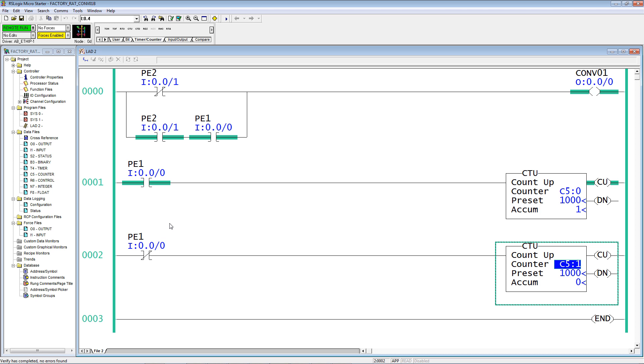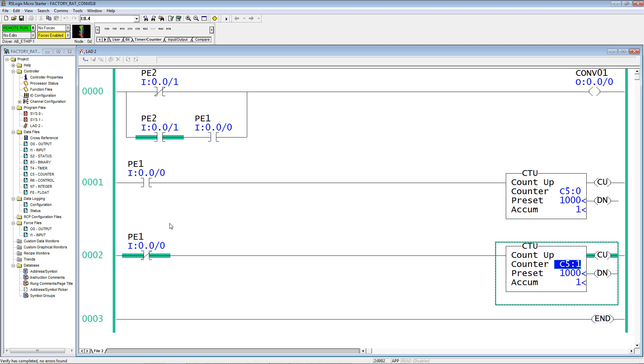Now, as that carton travels onto the conveyor and clears photo eye 1, look down at C5-1 and see what it does when it clears. Now, if you were going to count cartons onto the conveyor, would you count them when they arrived at photo eye 1, or would you count them when they left photo eye 1 and were pulled onto the conveyor? So I'm going to eliminate one of these counters.